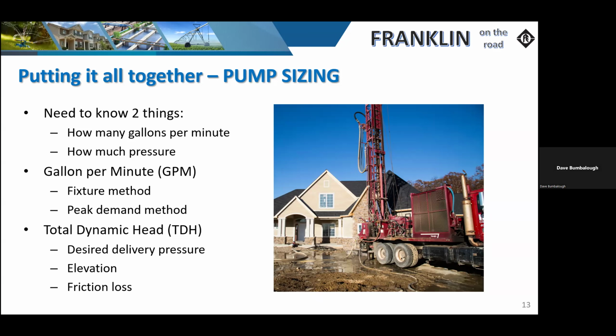And therefore, if we've got an application where, say, a bathroom is at the end of the hall, clear down at the other end of the house, opposite of where the water comes in, it may not flow the water properly, and/or multiple items inside that bathroom may not be able to be used at the same time without seeing a pressure drop. That is due to the size of the pipe, the restrictions, things like that. So it's in everyone's best interest to have a good relationship with the building contractor. Now, granted, if that cannot be addressed, then sometimes we may have to crank that pressure up just to offset friction losses.